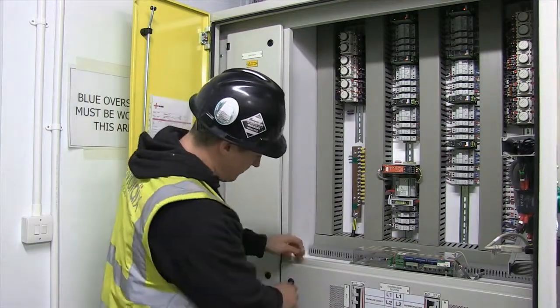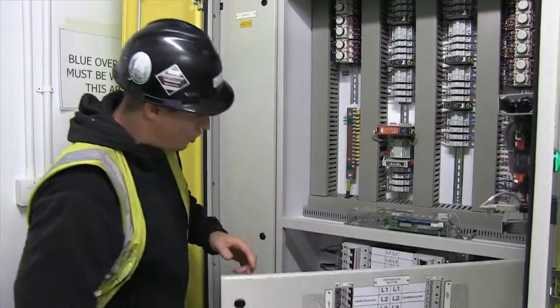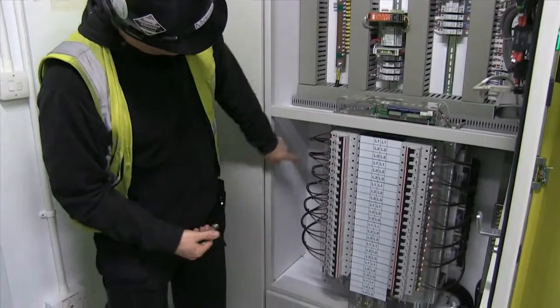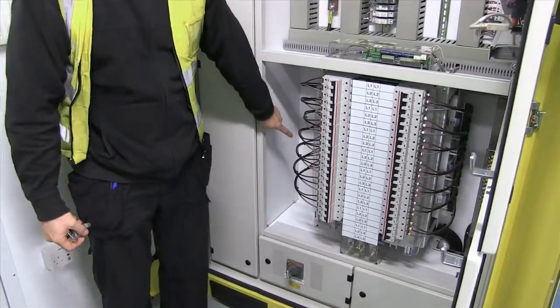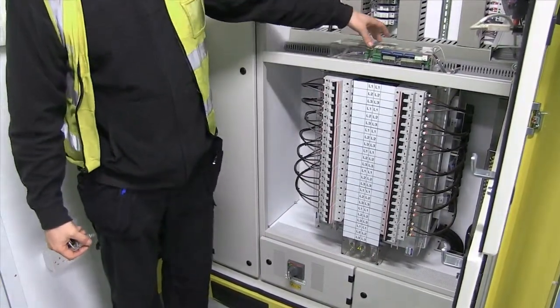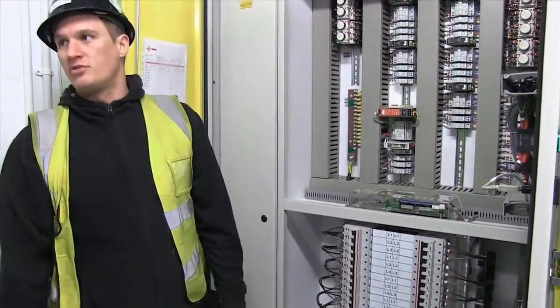And then the BPMs, like I said earlier, this is the BPM. What that does is it monitors all your outgoing ways. You can see the little individual CTs back there. And all that information goes to there. That information then goes off to the HMI, and that's what you see on the screen. Lovely little screen.